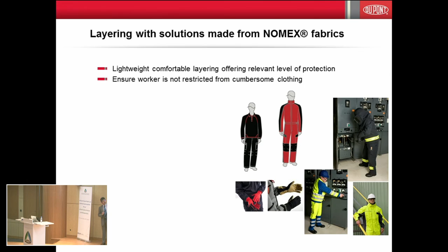Looking at body protection, it's important that arc rating garments are also FR. A fire-resistant garment is not automatically arc rated, but an arc-rated garment is automatically fire-resistant. These notions are important because they go together when looking at arc protection.